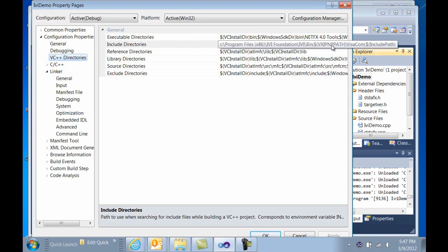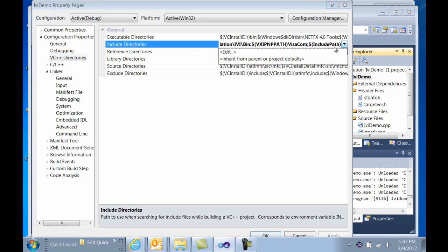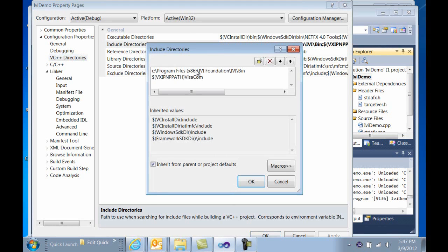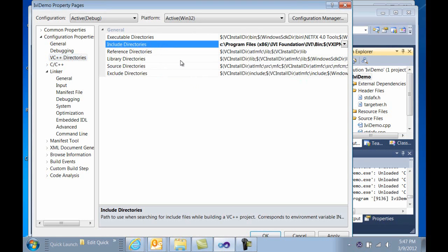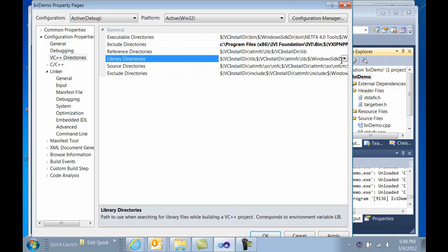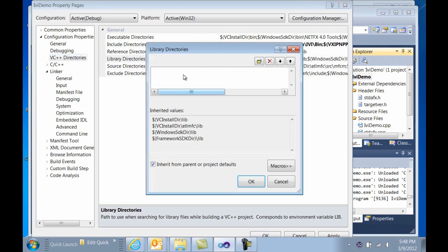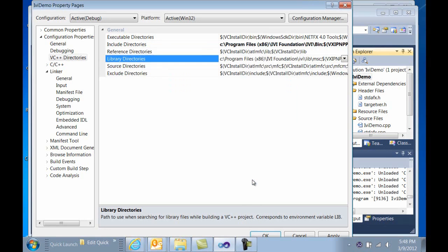I'll go through again very quickly some of the differences if you're using an IVI-C driver. We're still using the same DMM, but we have a number of new directories and files to include to make sure we can use them in our program. This second entry point will point to the correct VISA directory. And that's regardless of using 32 or 64-bit systems.